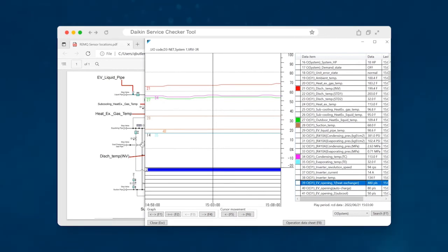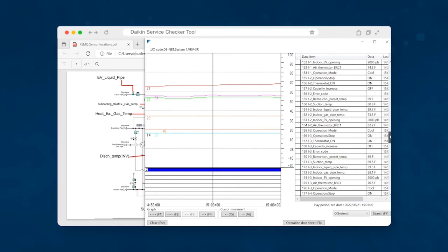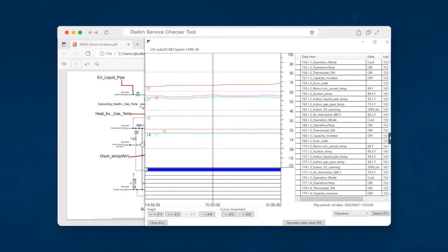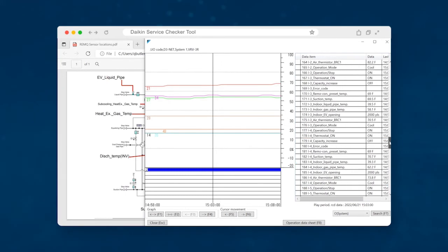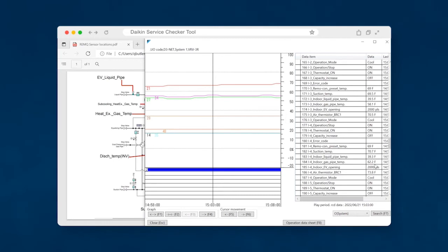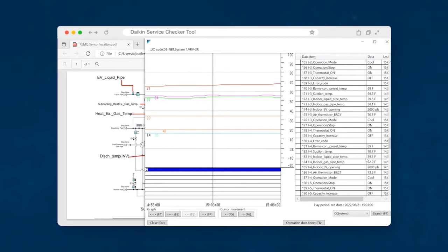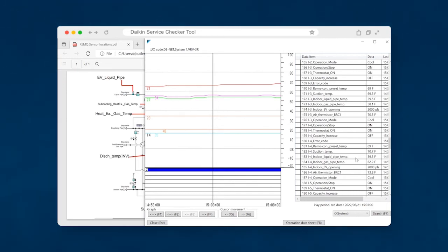One more thing that I just remembered in talking about evaporators. Take a look at your indoor units whenever you're looking for a low charge condition. All of these EEVs are at the 2000 pulse range. Now, 2000 pulses is at the top of the range. That means it's wide open, completely open. So, under normal operating conditions, the liquid and the gas pipe temperature should have about a nine degree difference between the two. A lot of people get stumped up on the liquid pipe temperature because that's not really a liquid pipe temperature in the conventional sense of the word. The liquid pipe temperature is actually a value taken after the expansion valve. So, basically, this is like a flash gas or a slurry mixture.